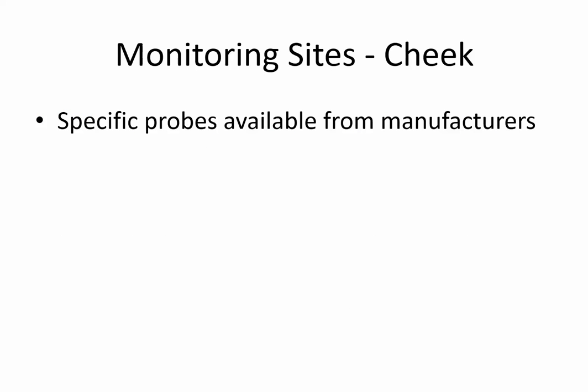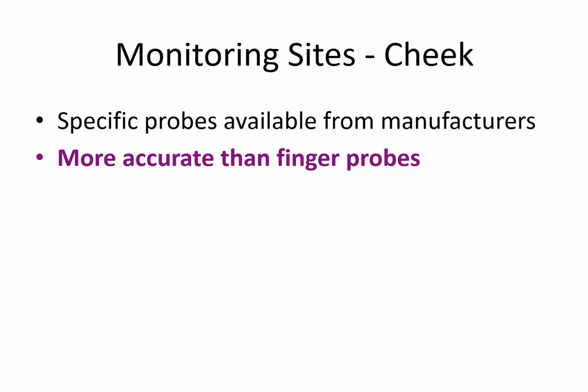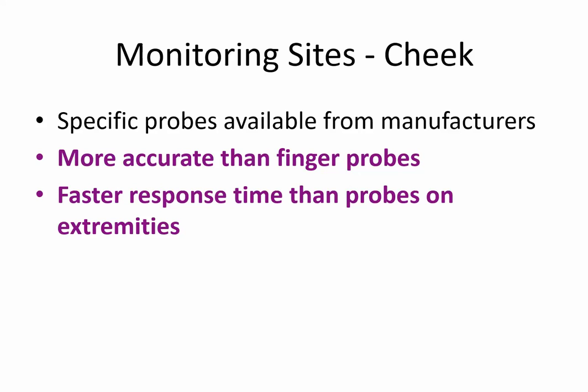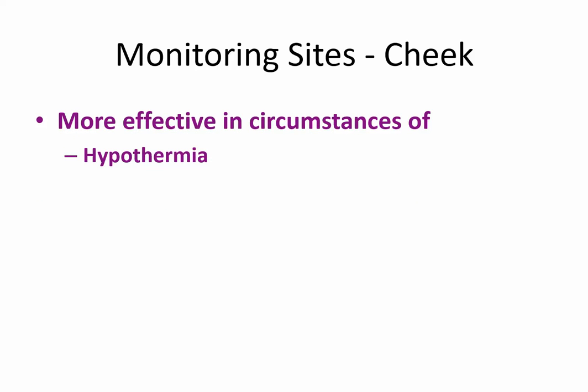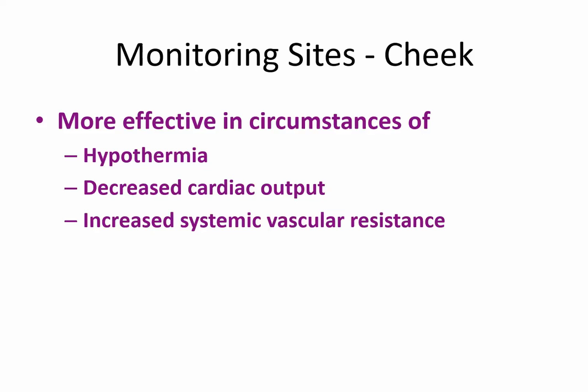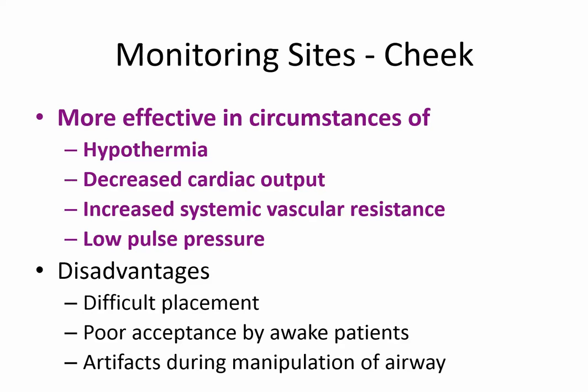There are specific probes available from manufacturers for monitoring pulse oximetry at the cheek. They tend to be more accurate than finger probes if you can actually get them to work. They have a faster response time. They're more effective in circumstances of hypothermia, decreased cardiac output, increased systemic vascular resistance, and low pulse pressure. But they're difficult to place, they have poor acceptance by awake patients, and manipulation of the airway can result in artifacts.